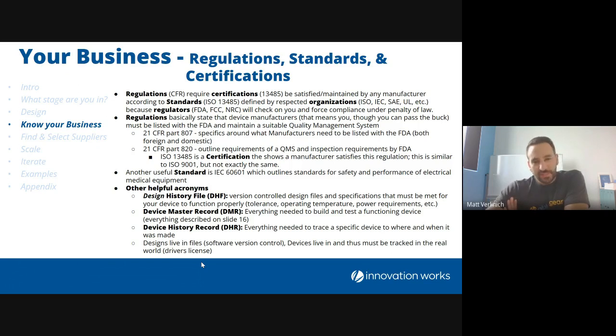And that's because if your device emits an electromagnetic signal, it can cause direct or indirect harm. Indirect harm by interfering with essential communications, which could be saving somebody's life, or direct harm, which is the typical worst case example that you hear about, is stopping a pacemaker. So you sell an electronic widget that just so happens to be sold to somebody with a pacemaker, and it stops their heart and they die. That's why FCC is sort of a bit higher than food, because it's a more acute problem.